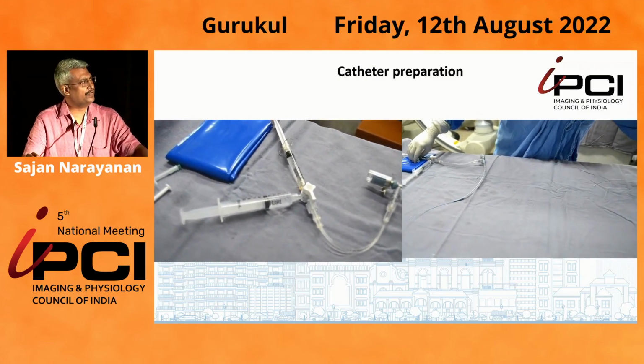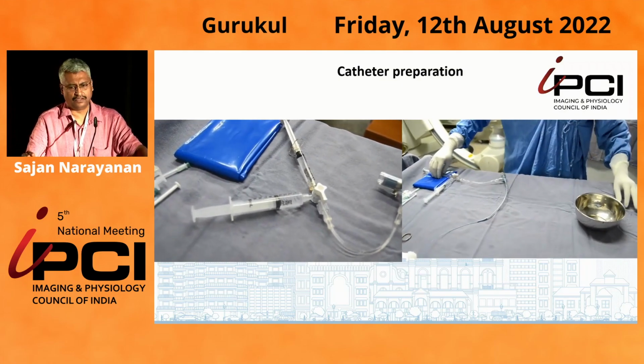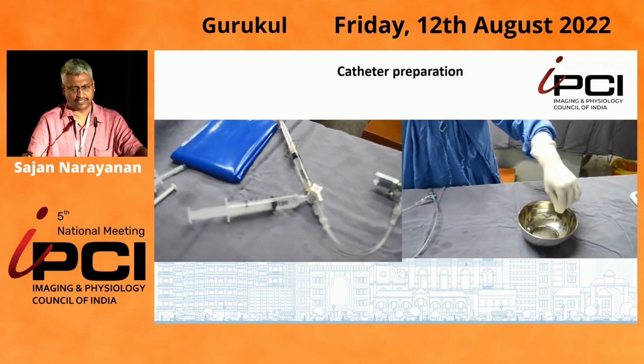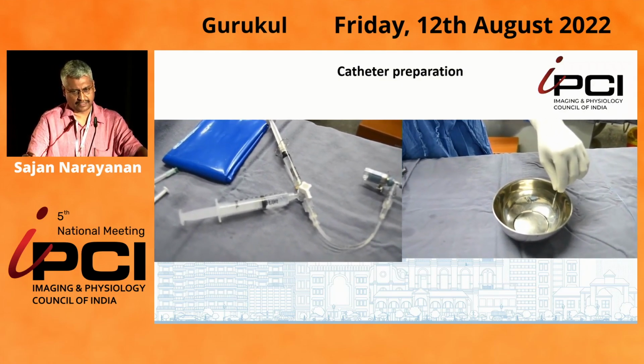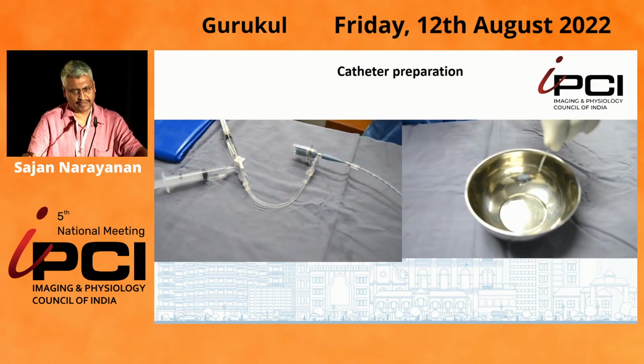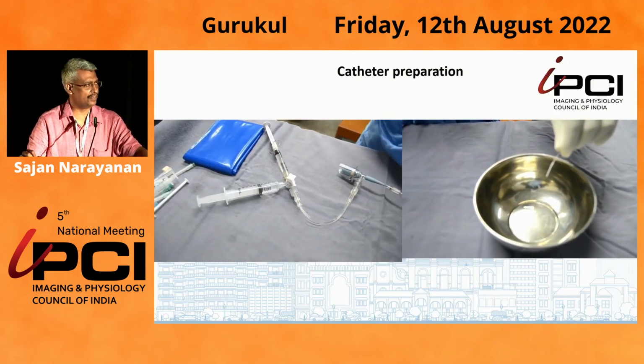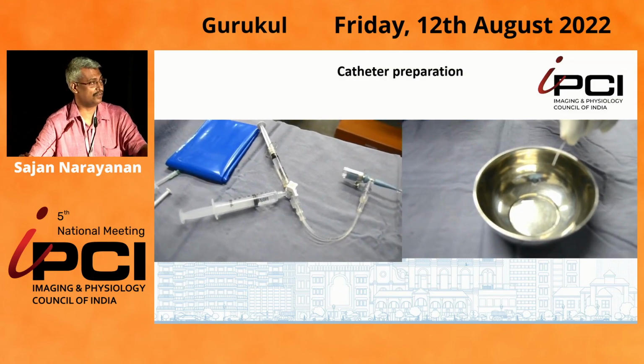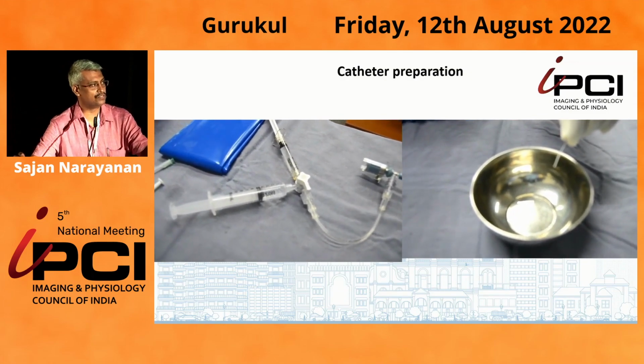That is shown in the video on the right side of the screen. So that's how the operator flushes it, and no air bubble exits. So make sure that no air bubble remains there. It can interfere with the image acquisition. It can scatter ultrasound waves and can produce false shadowing.